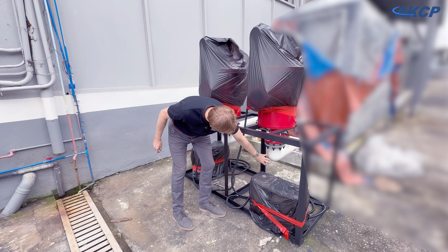So here we have our two self-cleaning filters. They're not connected up yet, but they've been mounted and they've got the pipe connection on the bottom, but the output not yet done. So basically, we run two of these in parallel with each other so we don't get as high a pressure drop, but one is actually sufficient. So we can run the whole system off of one, which means if one is being cleaned or is out of service, we can bypass it. We have some valves and we can shut off one of these while we service it and run the data center through the other one.